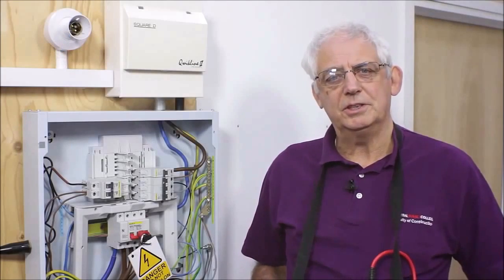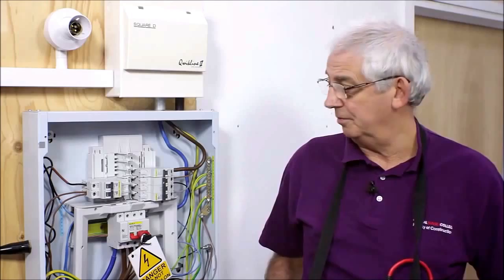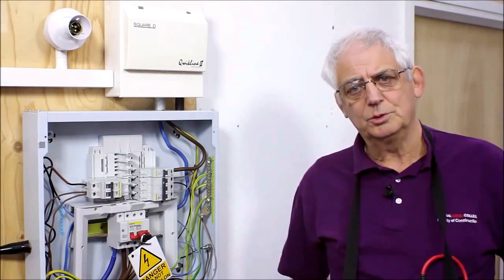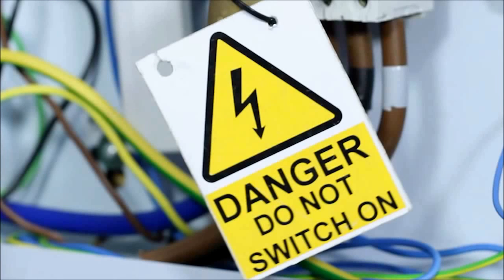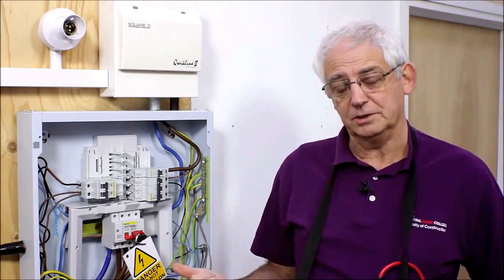I'm going to do an insulation resistance test on a 3-phase board or 3-phase installation. Rules apply always, of course, that we've got to make sure it's safely isolated because it's a dead test and we need to use the right type of equipment. Before we start, we need to make sure that anything that could be damaged by the test voltage is disconnected, isolated or bypassed. Any dimmer switches are bypassed, lamps removed if possible. Just those sort of precautions for two reasons. One, we don't want to damage the equipment, and two, it will give us false readings anyway, and we'll be looking for a fault that may not be there.